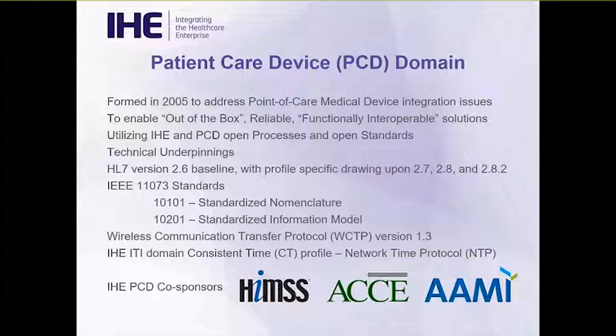For object models and nomenclature, it should be noted that the IHE PCD uses IEEE 11073 standards, most notably 10101 for standardized nomenclature and 10201 for informational models. And that'll also be referenced a bit more later in this presentation as it applies to particular profiles.